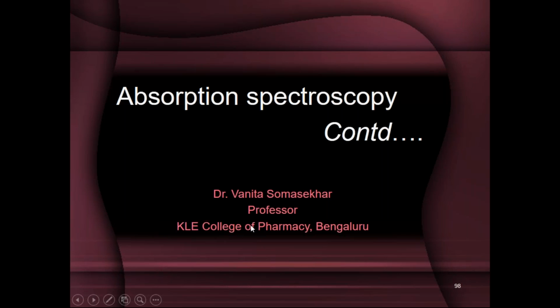So if you use a good wavelength selector, you could make the radiation incident on the sample more monochromatic and avoid the problem. And also, if you reduce stray radiation by keeping all the transparent components clean, optically transparent, by maintaining them well, we can reduce instrumental deviations.